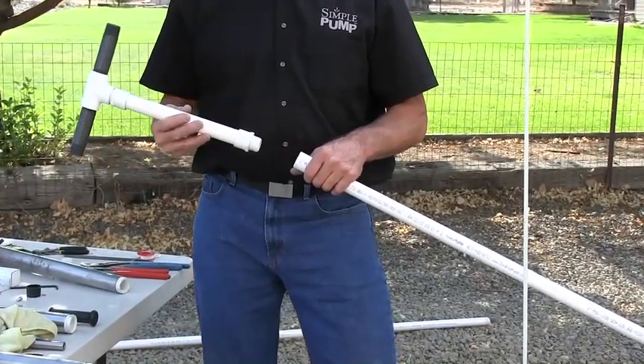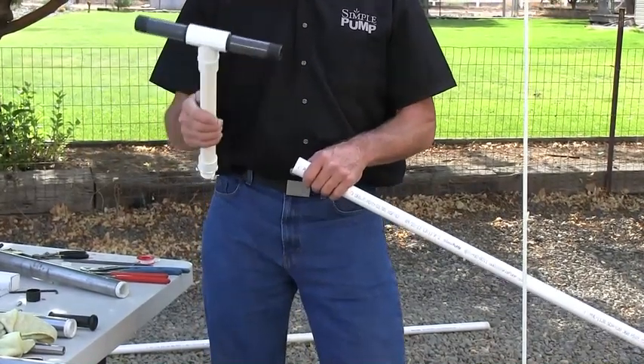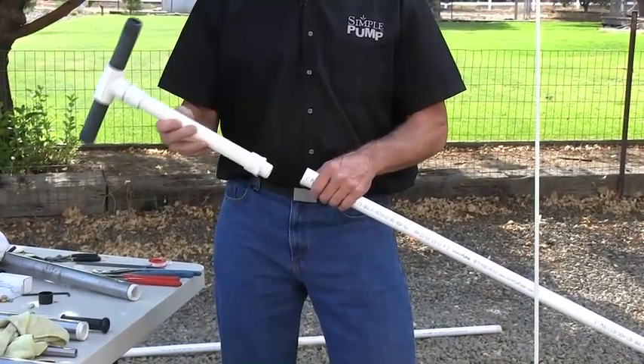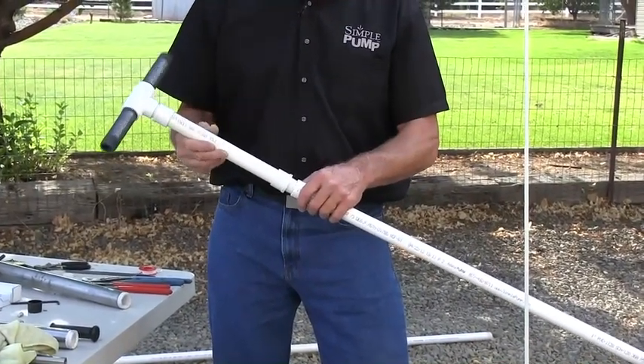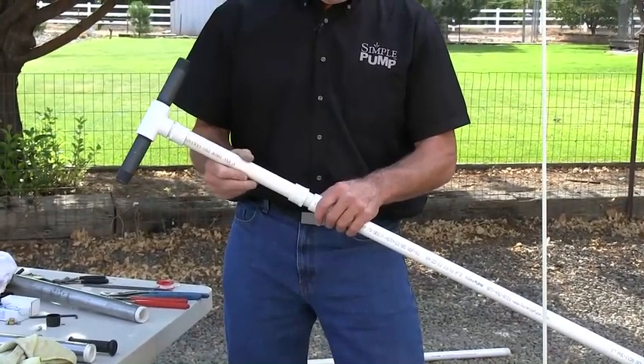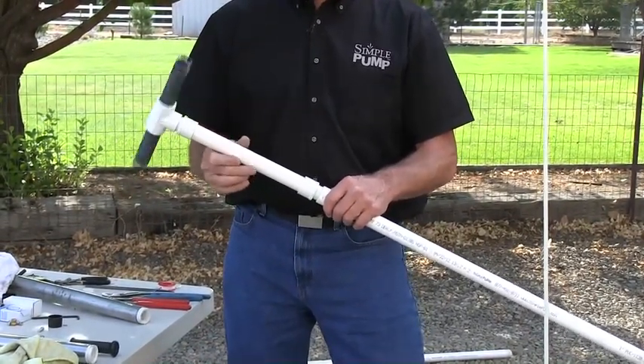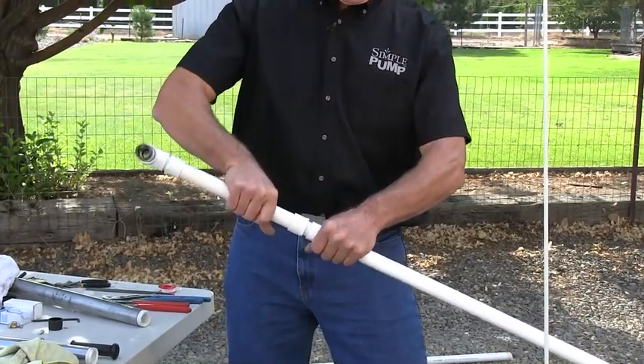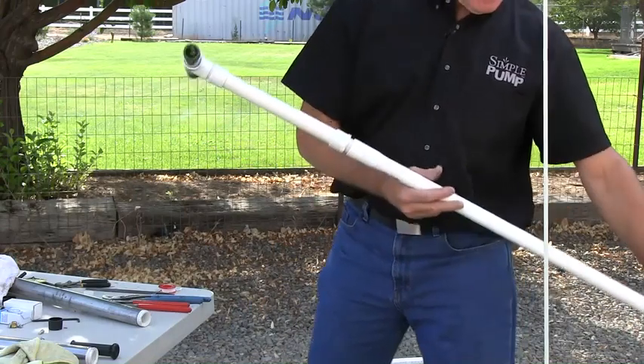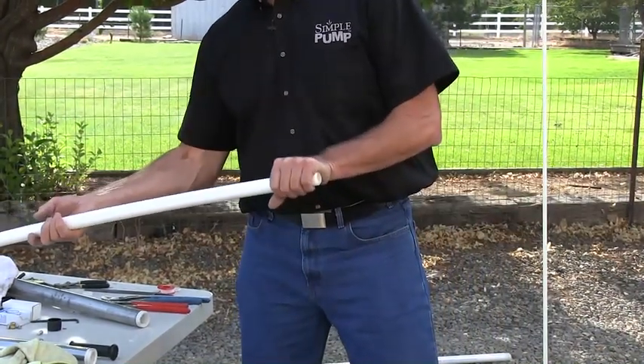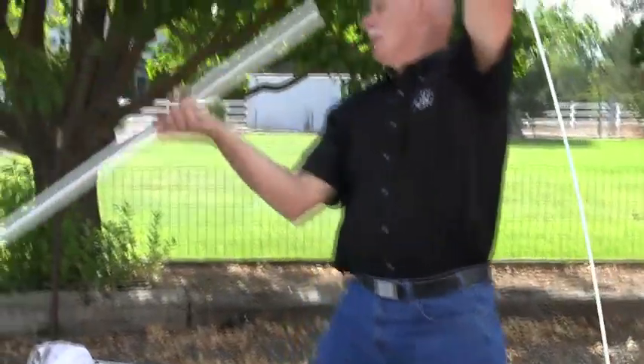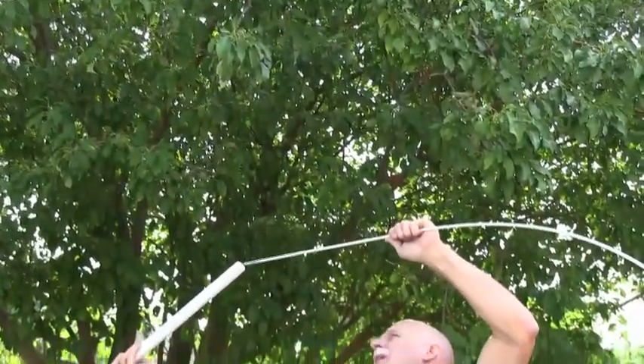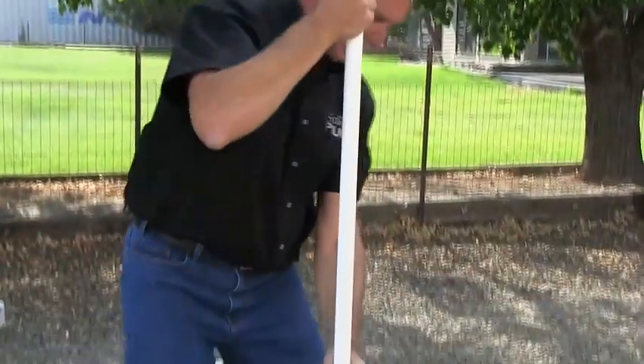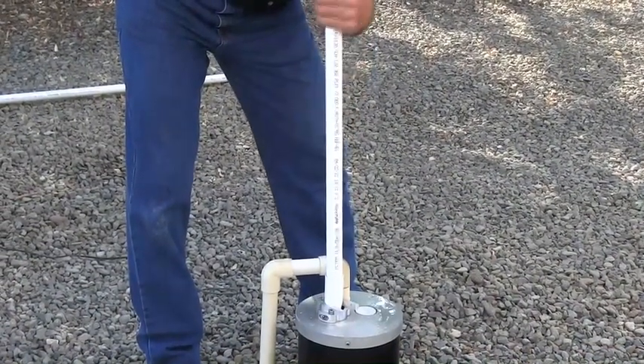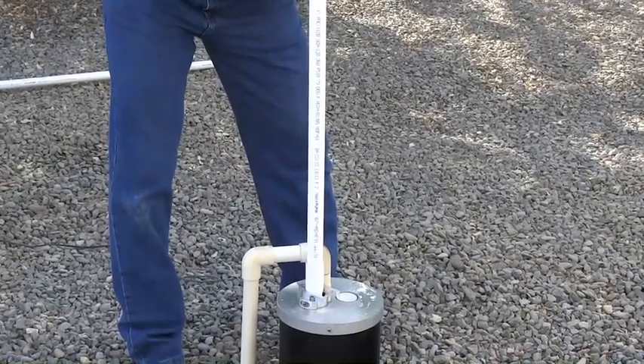On all simple pump systems with more than 12 drop pipe kits, we always quote and include a T-handle assist tool for the residential installer. The T-handle assist tool changes the relationship between you and the pipe to where it's more like handlebars on a bicycle or weights at a gym. It just gets threaded into the upward female bell end, and then we bring the end of the pipe over the rod end. The Teflon tape would have been applied to the threads in advance, and we bring it into position. We thread the male into the female.